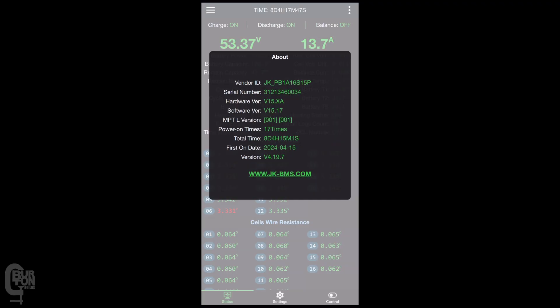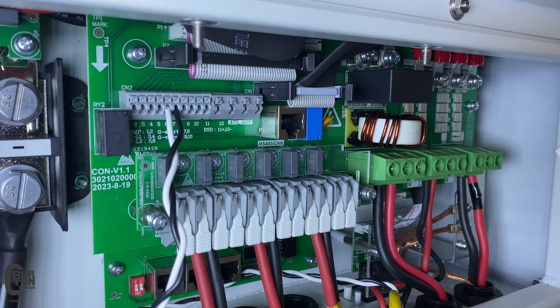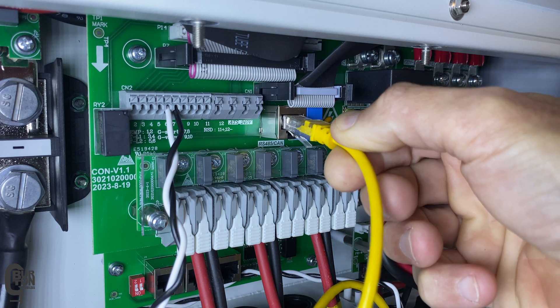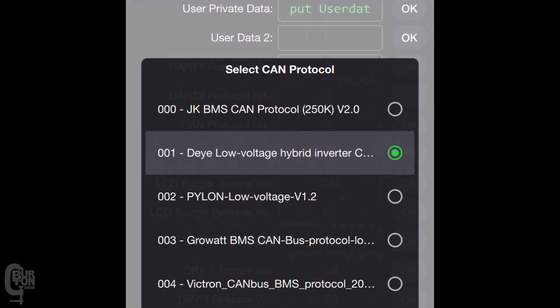This is hardware version 15 of the JK Inverter BMS, running firmware version 15.17. It's connected using CAN communication to a SunSync inverter, and the CAN communication protocol is 001 Deye low voltage hybrid inverter, which has been set in the JK BMS app.